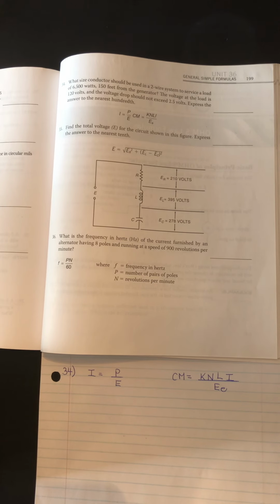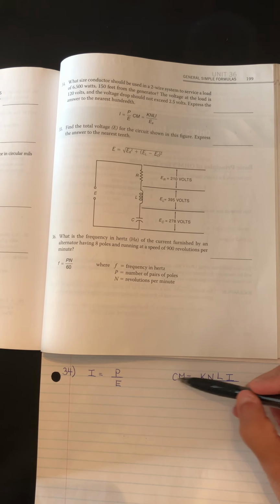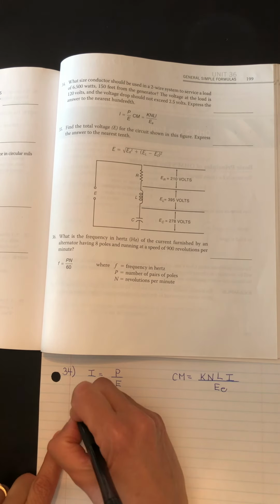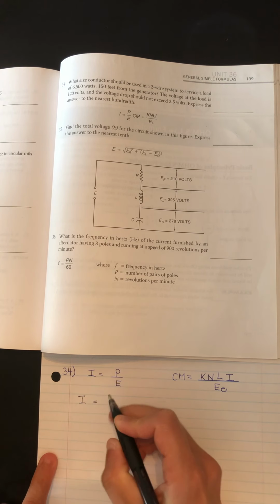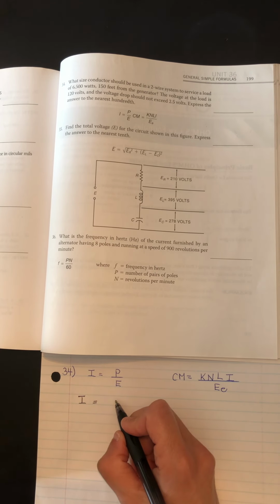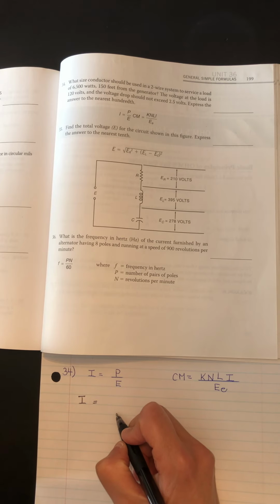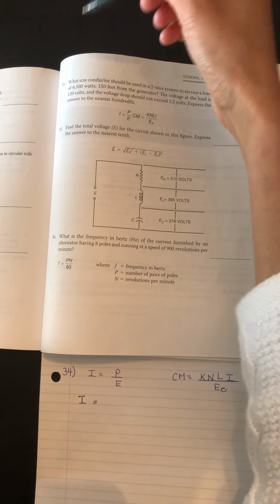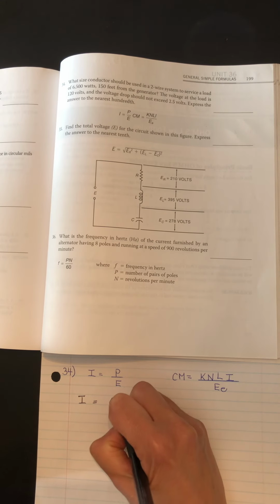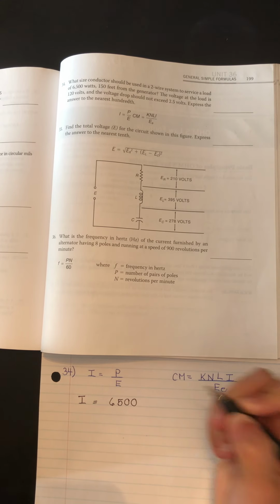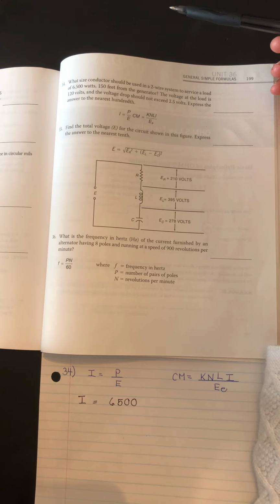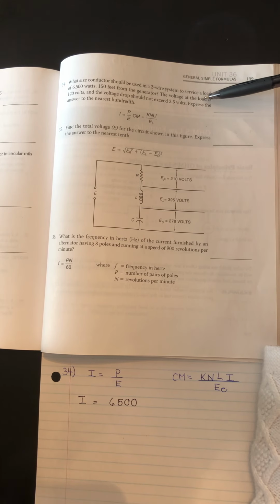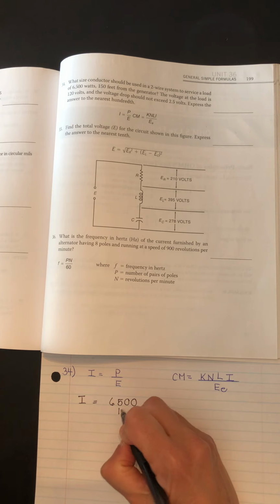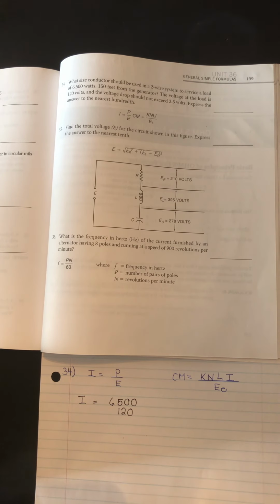So what we're going to do first is calculate the current, because the current is needed in this formula for the cross-sectional area. So let's begin with this formula here. So we have to take the power and divide it by the voltage. So in this case, we've got a power of 6,500 watts, and we have to divide it by the voltage. It says the voltage at the load is 120. So we start with this calculation.